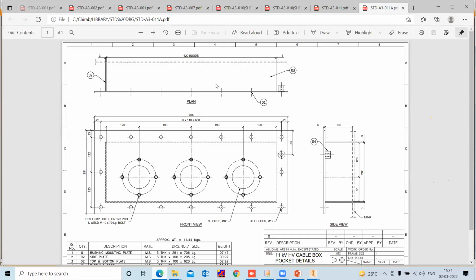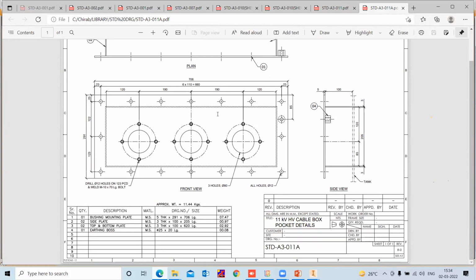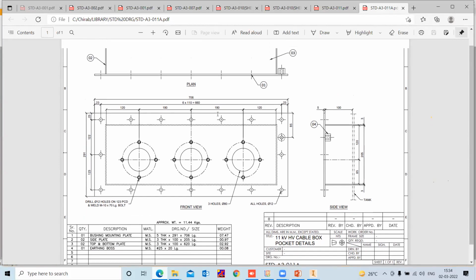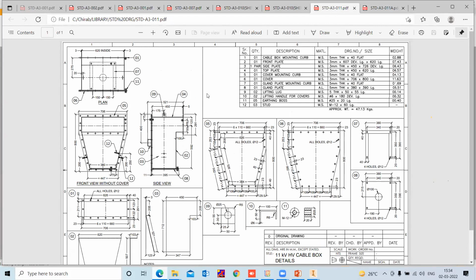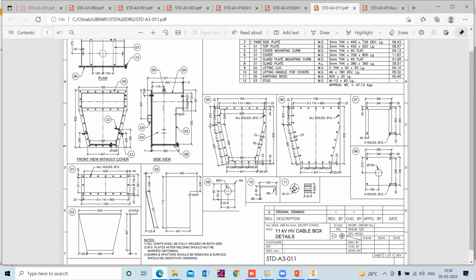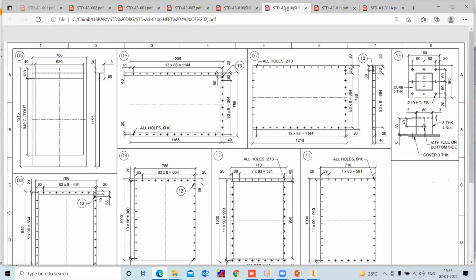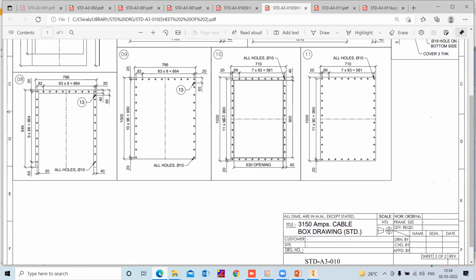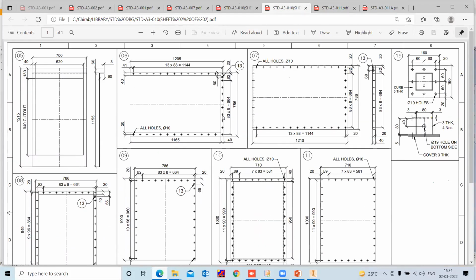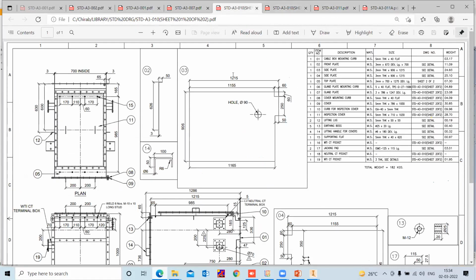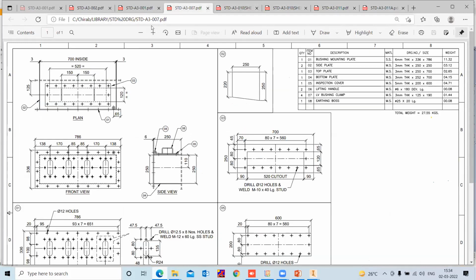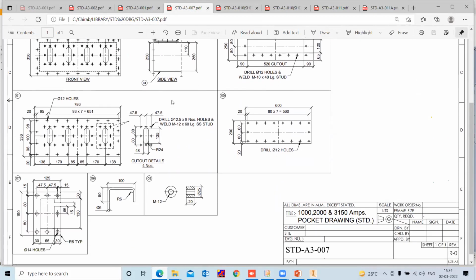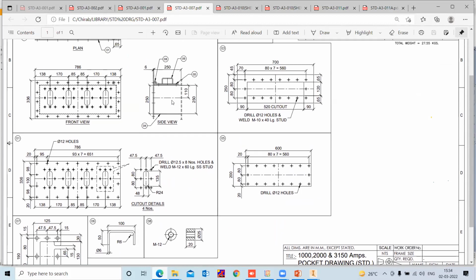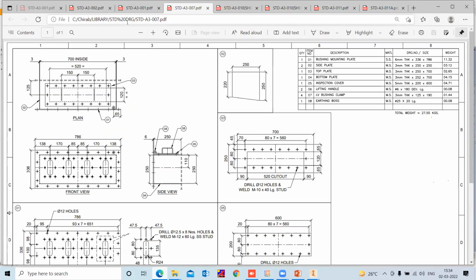On the loose part diagram, these are the diagrams for the cable box. One is for the pocket diagram. Another is a cable box diagram for the HV side, 11 kV side. And this is the cable box drawing for 3150 ampere rating. You can see if on the LV side the bushing type is epoxy type, then this type of cable box will appear.